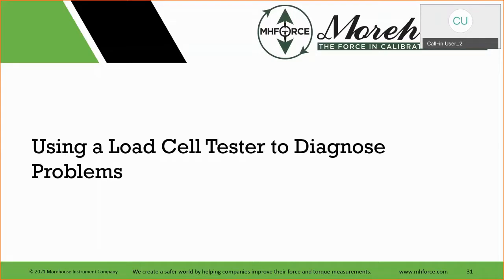So it does happen, even at every level. We are not immune to it. So that one. But what if the Cal Lab's not honest and they don't tell you, and then you get that load cell back and you don't know what's been done to it? You send it out. You have the load cell tester. You can send everything out. You can know it's good. When it's coming back, it should be good as well.